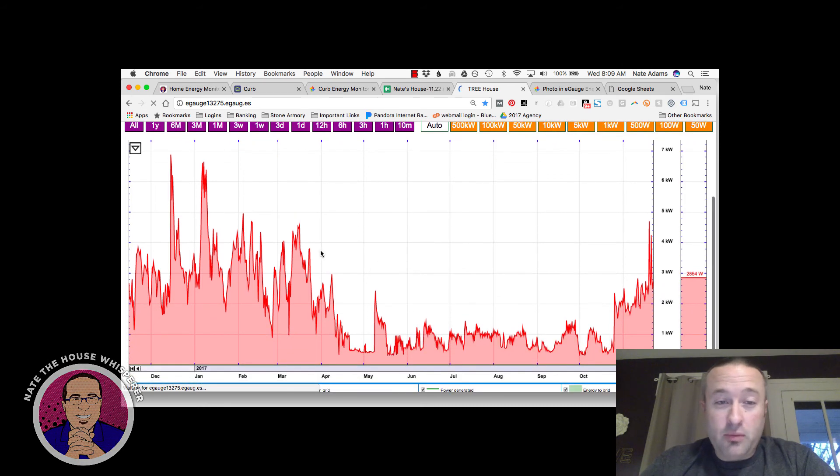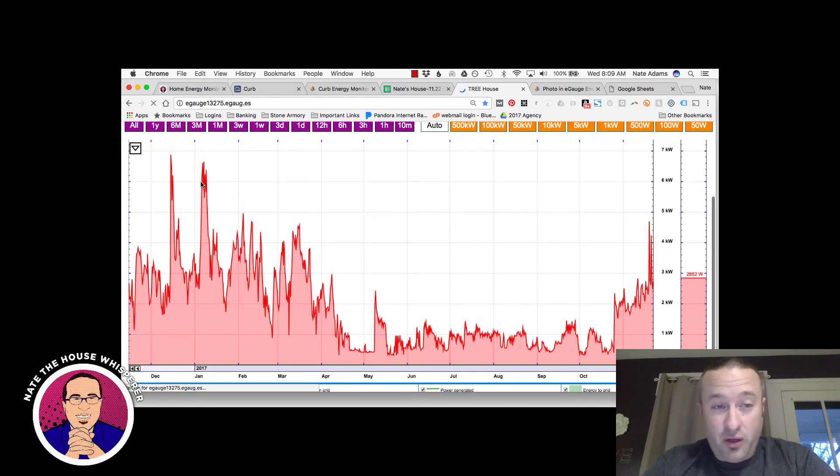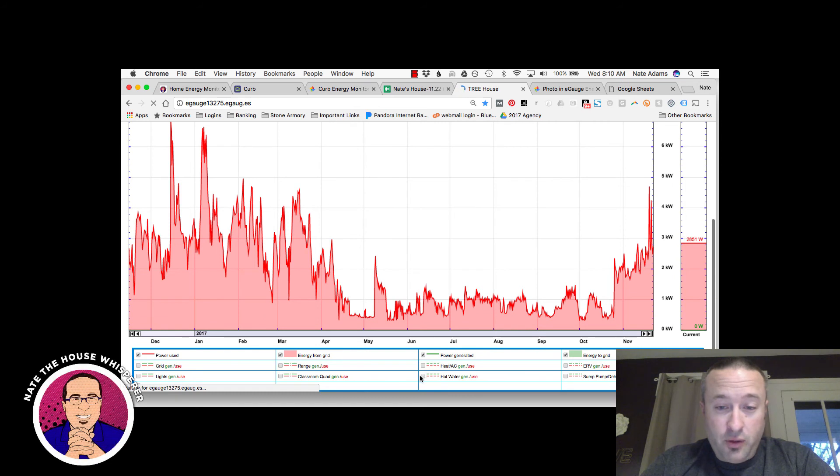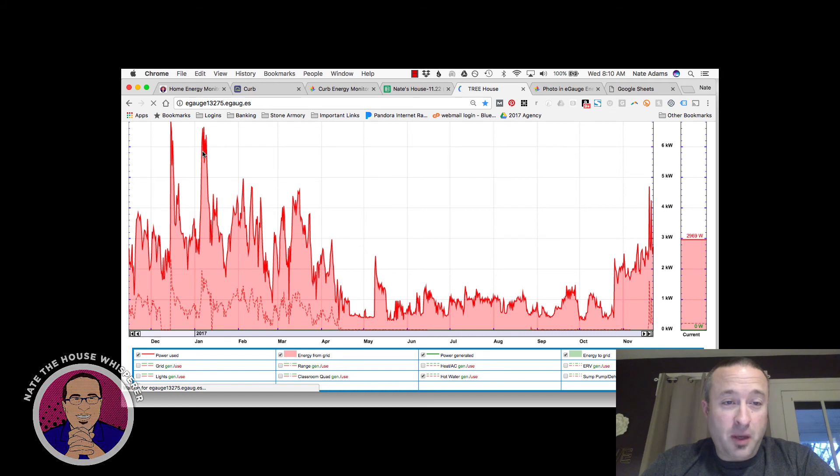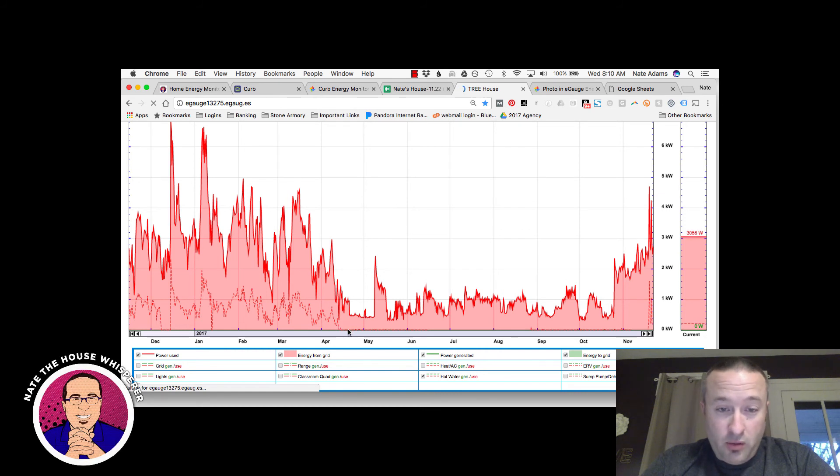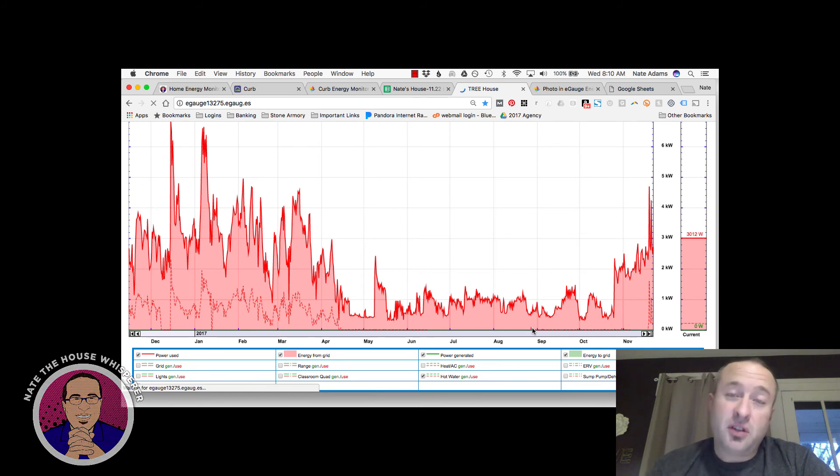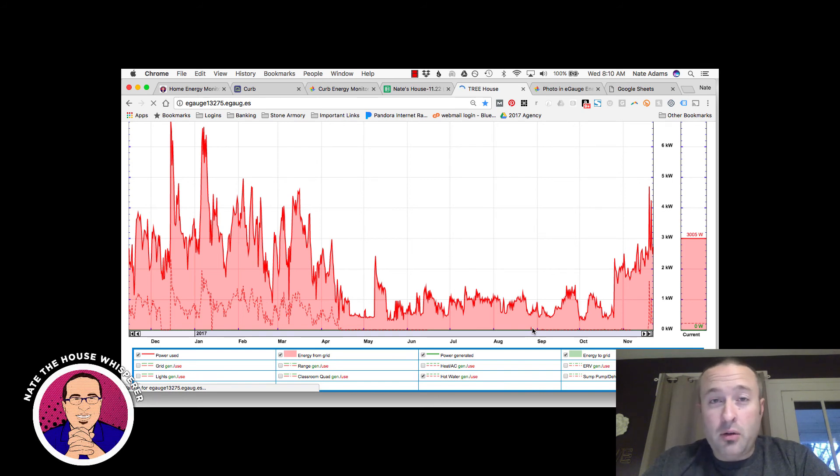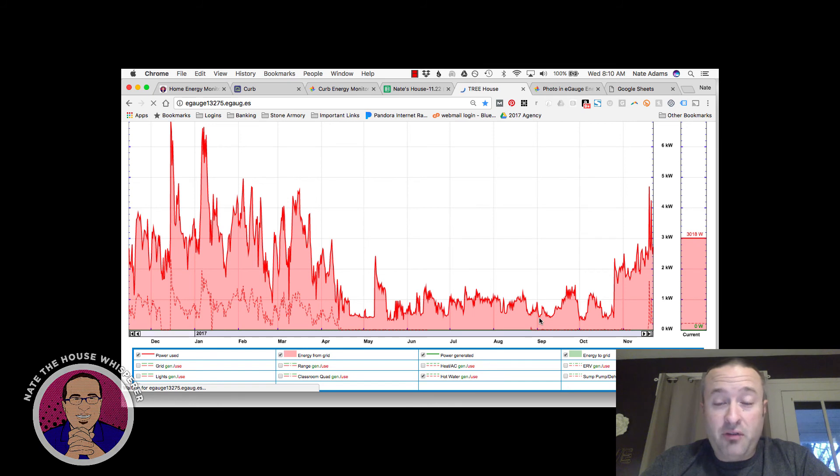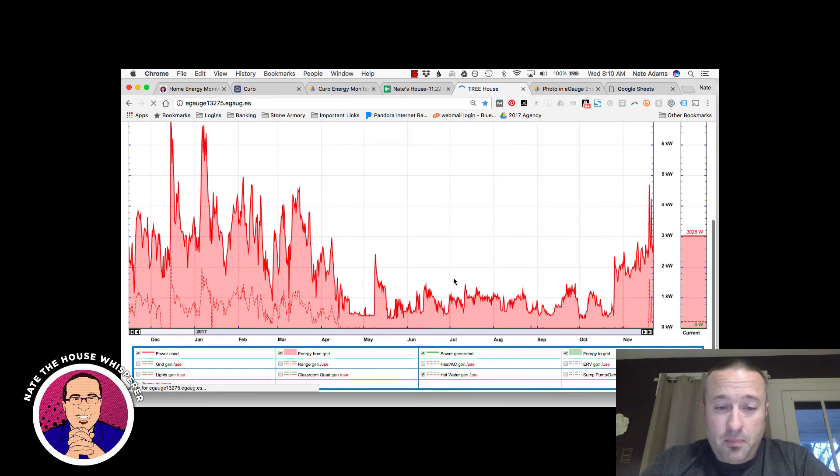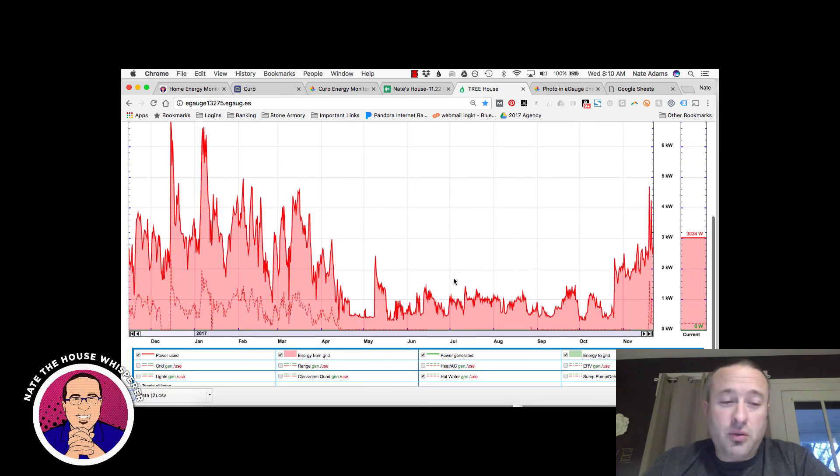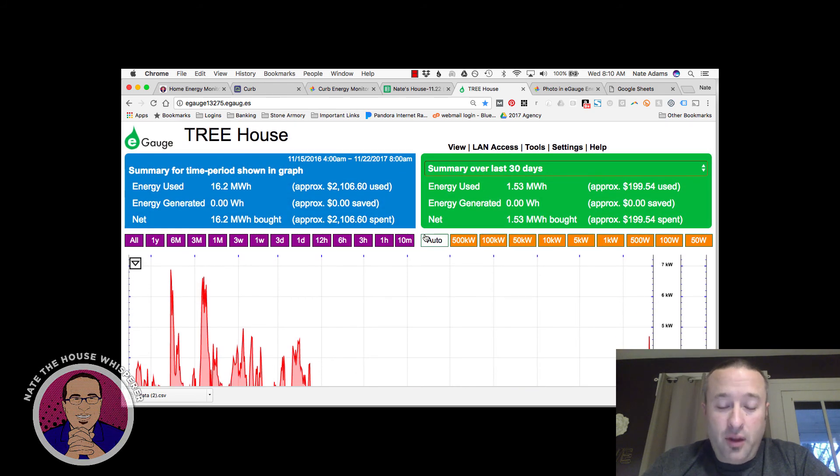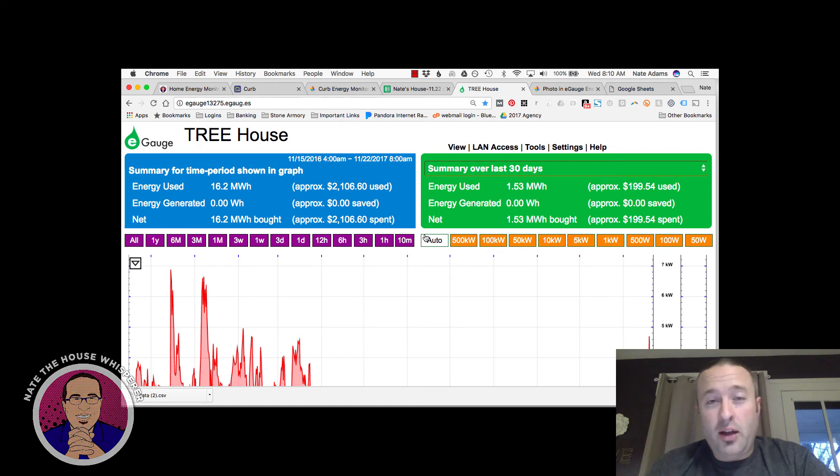What I tend to really like are data visualizations so I can understand what's going on and I can look for peaks and try and figure out what's going on here. Which I believe, for example, you can see where the spikes get particularly high, the electric floor heat was on. And then you can tell once the weather got warm, finally the hot water heater and the electric floor heat shut off. And you can see that basically there's no hot water use in this building at all, which makes sense. It is the environmental studies department. So the only people that are there are largely the three faculty members and the students. And particularly in the summertime, when there's no classes to speak of, there's really not much usage in that building. So this gives you a pretty good idea of what's going on in a building. And I appreciate that their data export is so good. So if you are looking for data export, the E-Gauge is a nice device to go with.